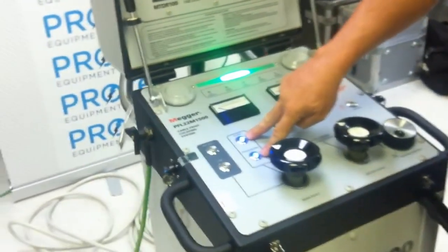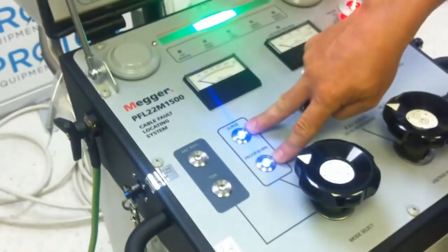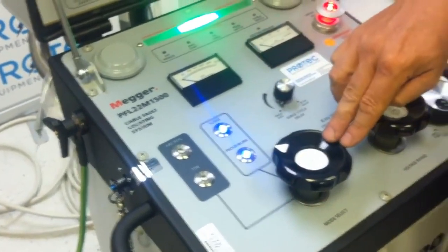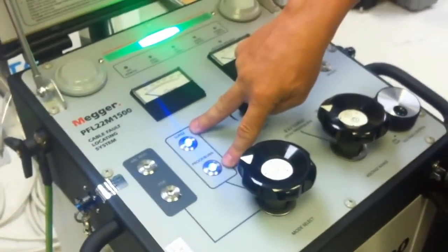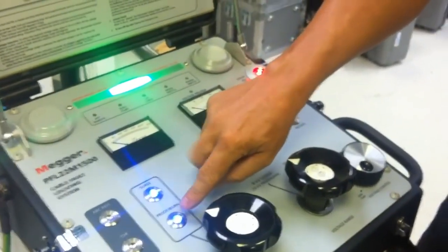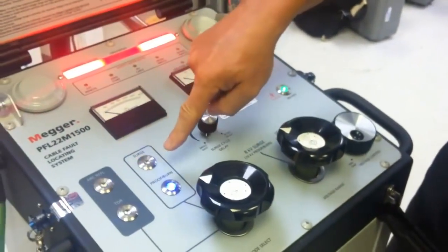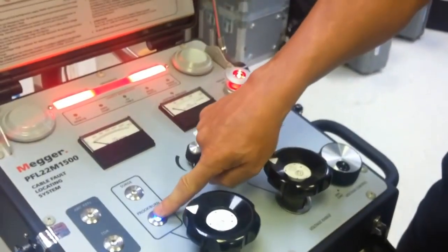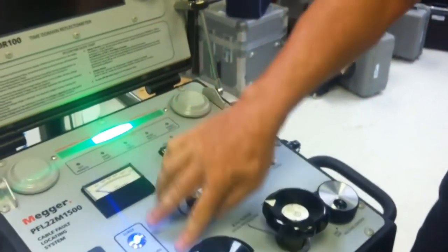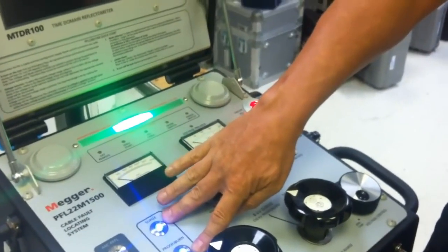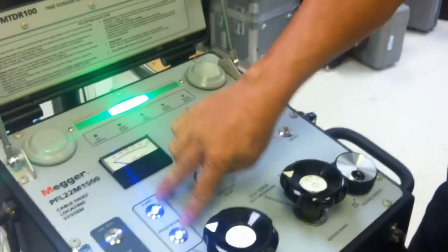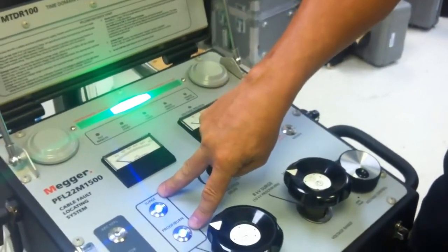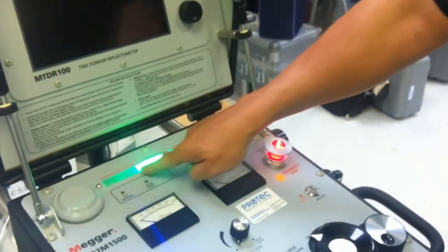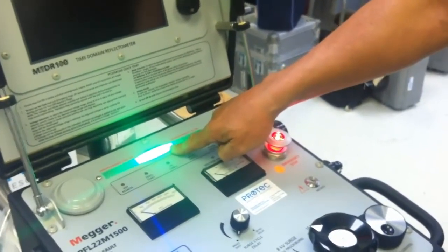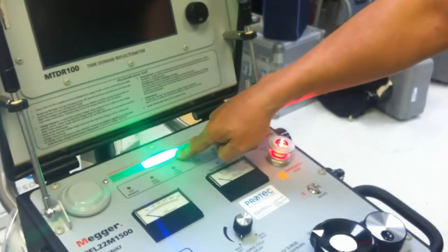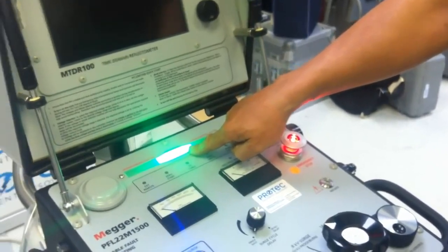Now you'll notice that the blue lamps are illuminated over here. So at this stage, it merely tells me that I've selected this section, but now to select a specific technique, I'd merely push the button, and you may have noticed that the mode select simply set to this position tells me that these are my two potentially active modes of operation. The system is in a safe earth-grounded situation where, again, this would be where I can safely handle the cables, safely make connections or disconnects.